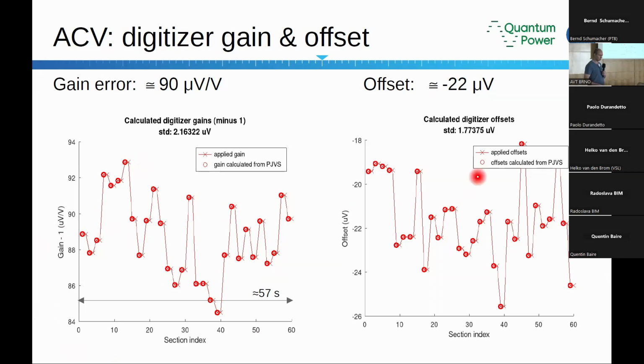This is the gain. Here is the offset. It was about -22 microvolts. But the most interesting thing is that the gain error of the digitizer was 90 microvolts per volt. It was not calibrated for a very long time. It was just not needed. It was usually used as a transfer standard or something like that. So I was quite happy that there is such a big error, so I can see that the system works.